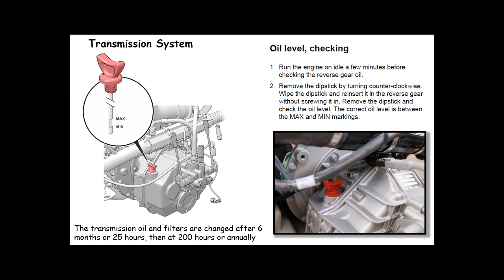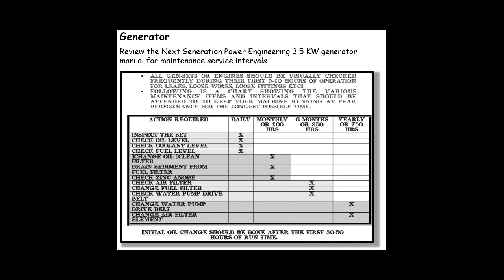This is the service protocol for the generator. They note that the oil change should be done after the first 30 to 50 hours of runtime, and then at 100-hour intervals after that.